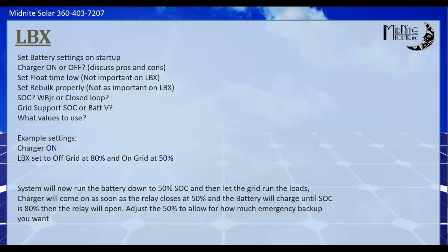So if you've got a co-op or a really, really picky utility, LBX is probably the way to go, because it's just absolute. The relay opens. There's no chance of anything going to the grid. Whereas in a grid support mode, you are actually selling a little bit to push the voltage up to overcome the utility to power loads. You're never exporting, or you shouldn't ever be exporting, but there is that nuisance export for a tenth of a second every now and then. And some utilities can see that.